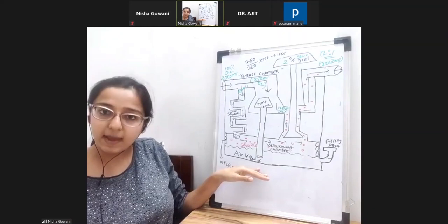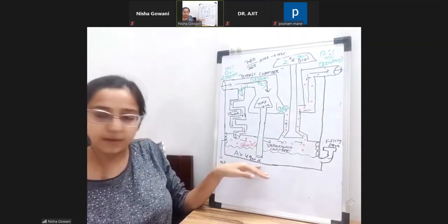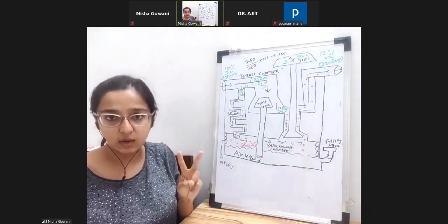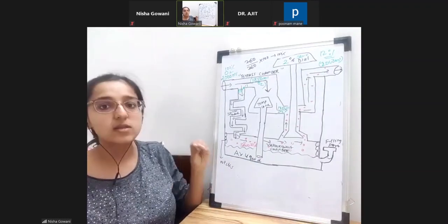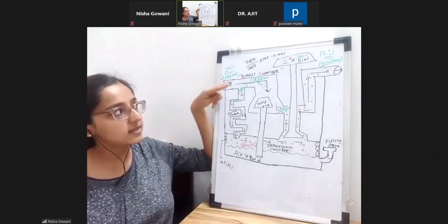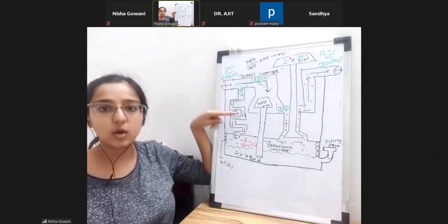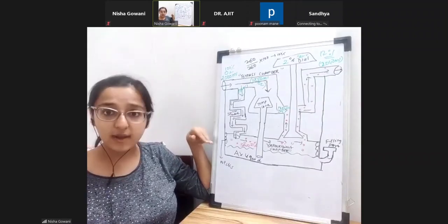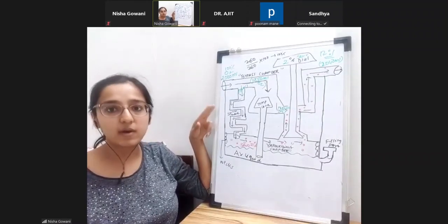So that can be a bimetallic strip, or you can have a temperature compensating cone. So these are the two, bimetallic strip and temperature compensating cone. And they are the ones which are going to again alter the splitting ratio. Although we have set it from the concentration dial, here also, as the temperature increases within the vaporizer or decreases, accordingly the cone will move up and down.